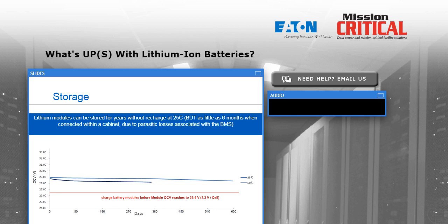If you look at the chart on this slide, you see the open circuit voltage on the left, and the red line is basically the lower limit—I don't want the battery voltage to drop below that while in storage. The horizontal axis shows the number of days; there's a couple of years of data here, both at 25 degrees C (the blue line) and 60 degrees C (the darker line). Even at 1 to 2 years of storage, we're nowhere near that red line limit for a lithium battery put into storage at 100% capacity on day one.